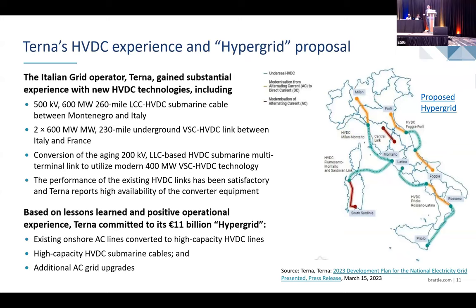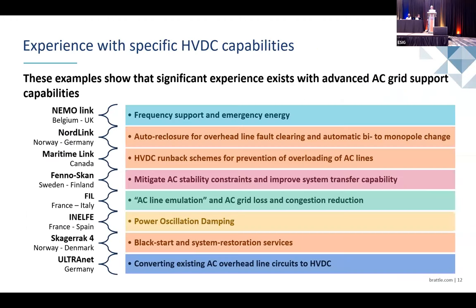Same for the Italian grid operator. They perhaps have the most experience with HVDC because they've used HVDC to connect to some of the islands that they have, but there are also several new VSC-based HVDC projects that they are very happy with. And based on the lessons learned with these projects, they are now committed to an $11 billion hypergrid, which you see on the map here. It's basically an overlay where a combination of HVDC lines, AC to HVDC conversion and upgrades of the AC lines will create an overlay that dramatically increases transfer capability throughout Italy.